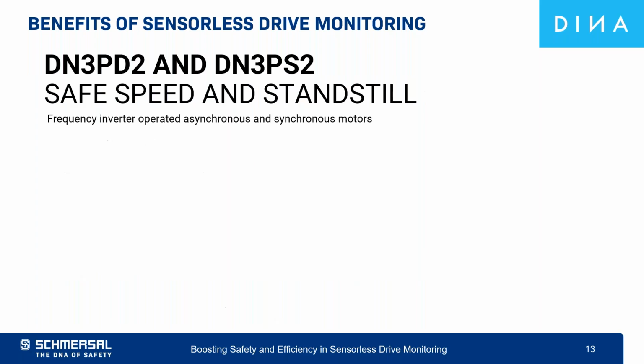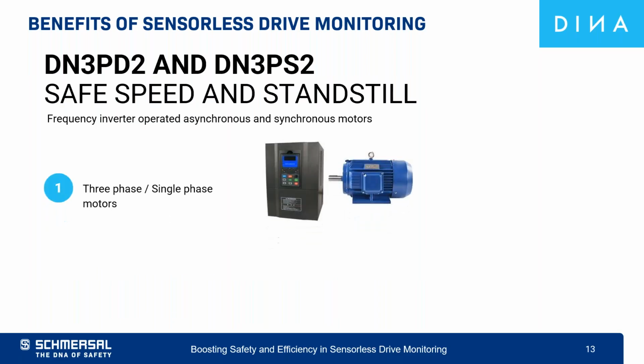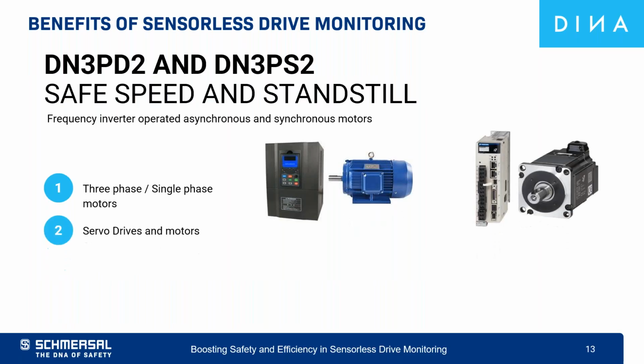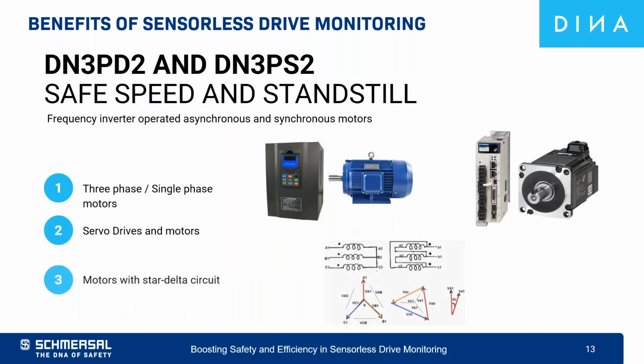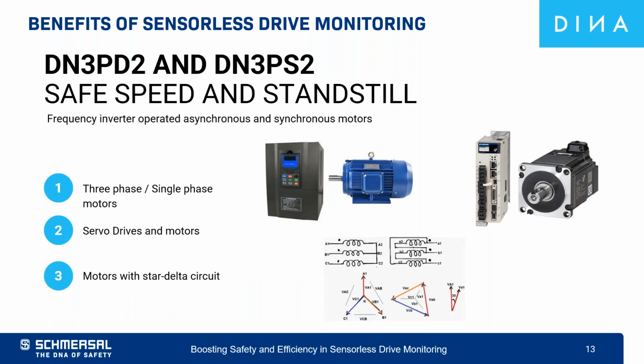Perfect. Okay, so both the DN3PD2 Safe Speed module and the DN3PS2 Standstill module boast flexible compatibility for different motor applications. They offer connectivity to three-phase and single-phase motors from 90-volt AC to 690-volt AC, including connection with VFDs, servo drives and motors, and star delta circuits for low and high-speed motor applications.